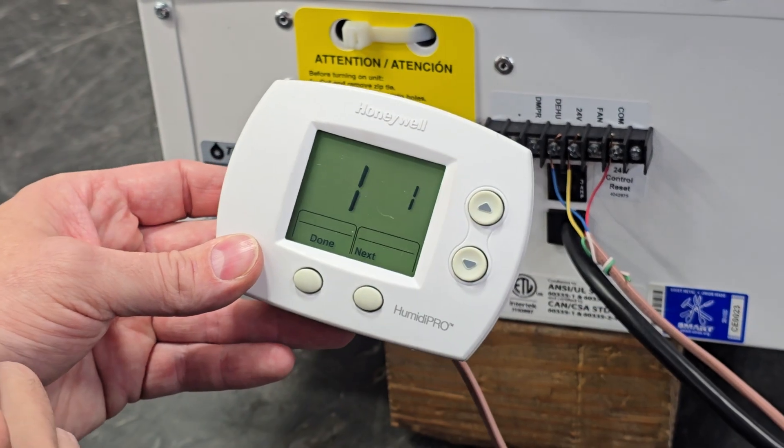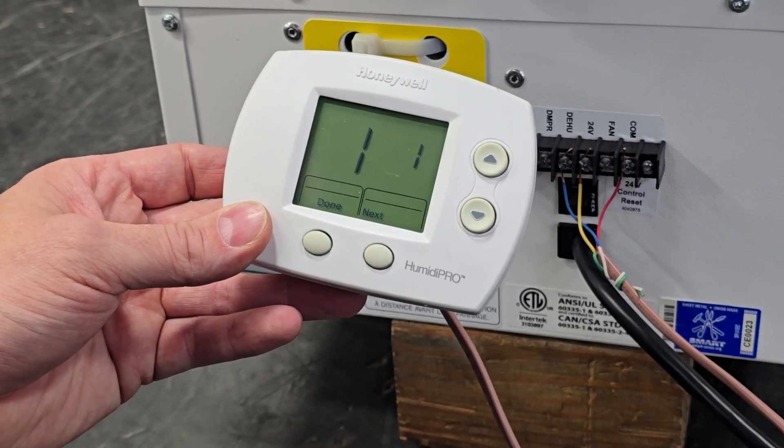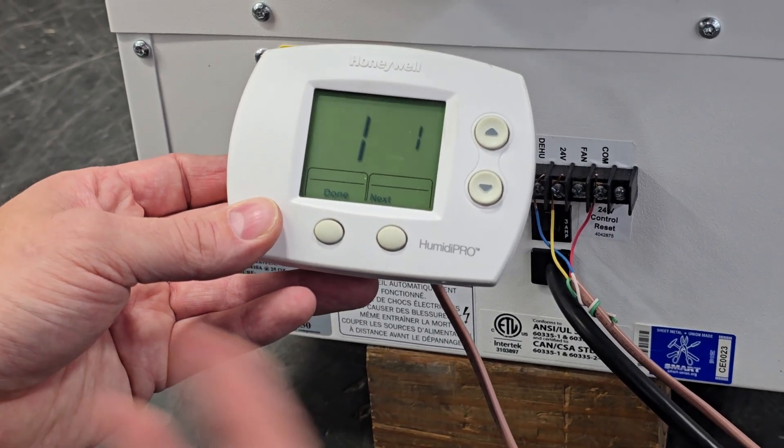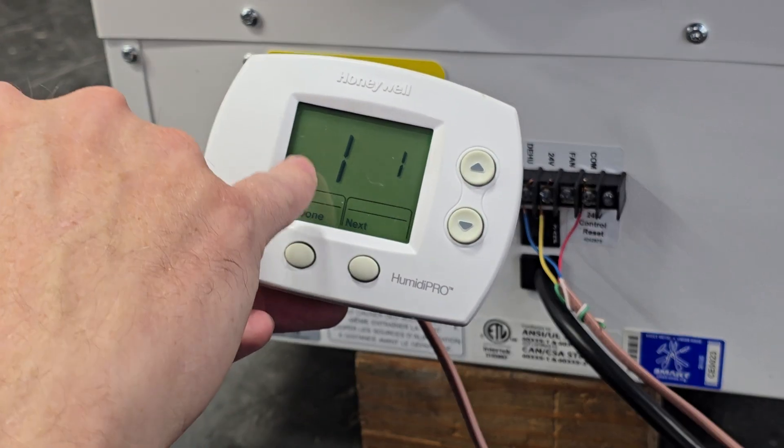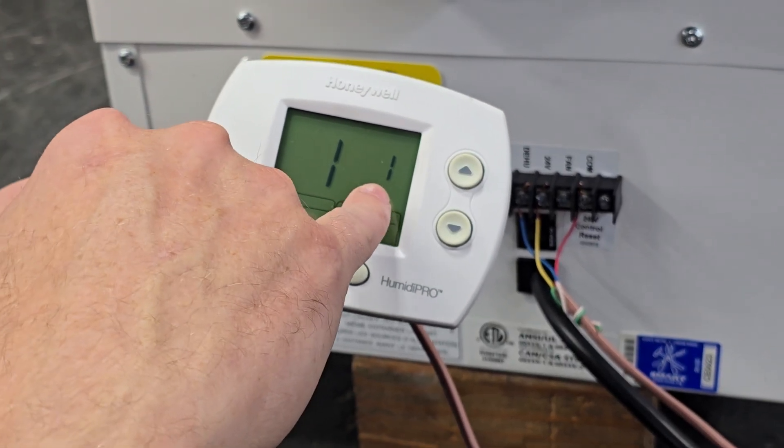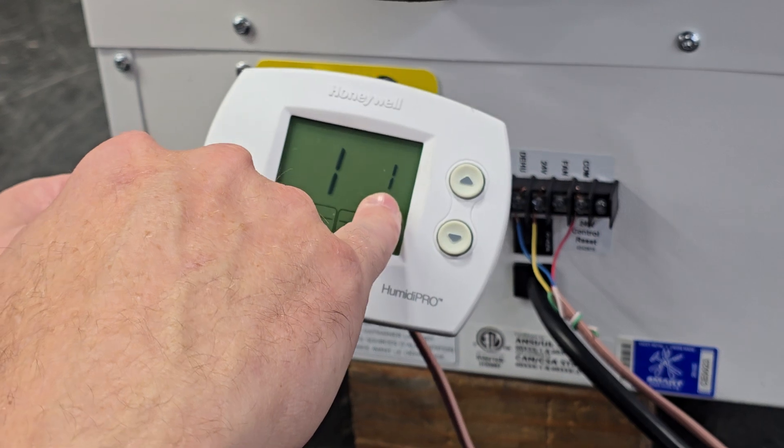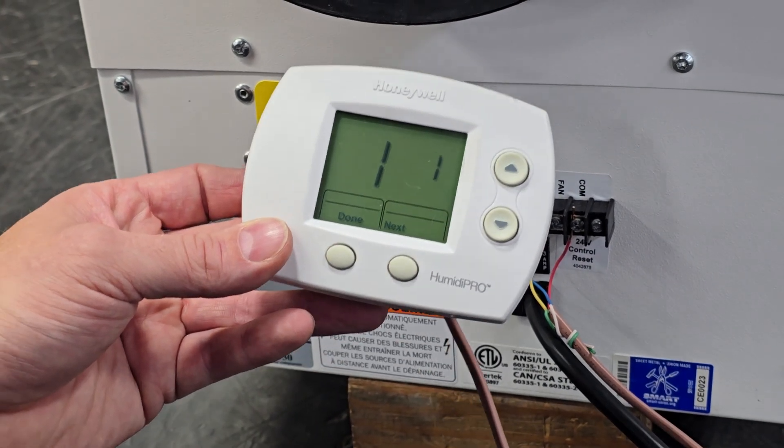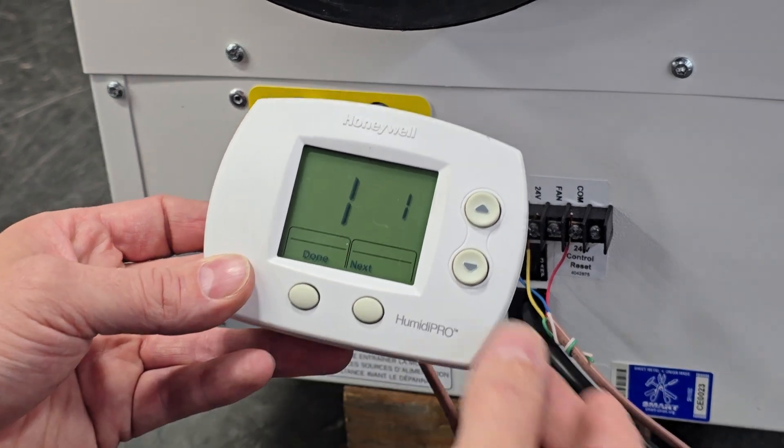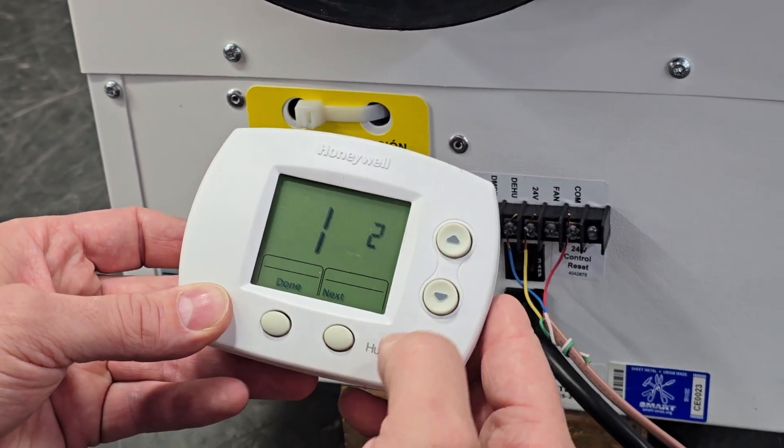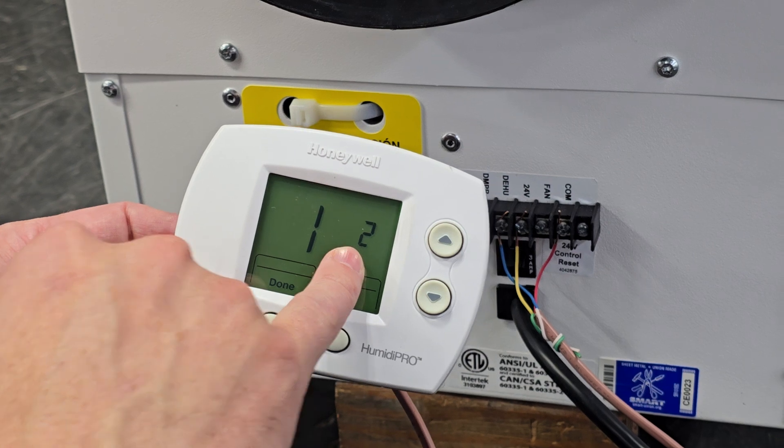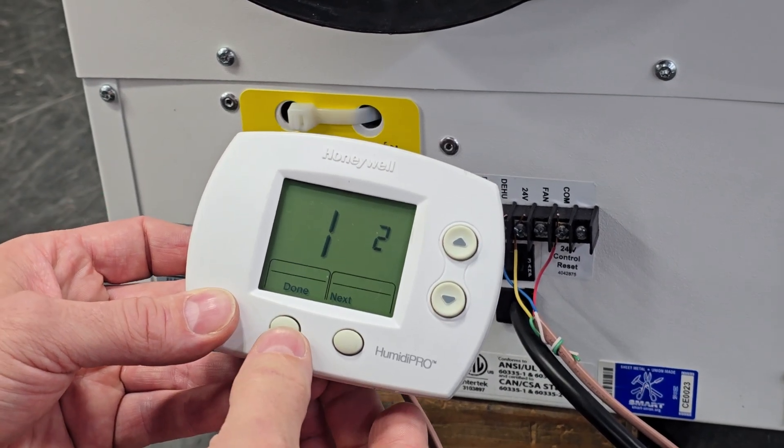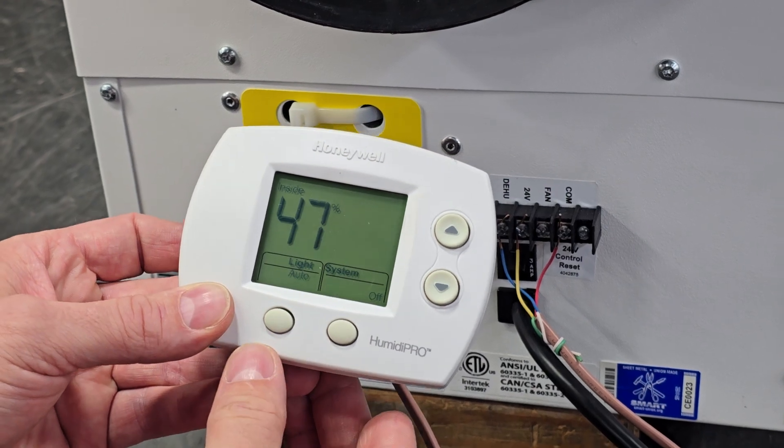These are codes for the different type of control function you want. This is the first function, this is the code on that function. It's set to 1. 1 is actually for a humidistat, so if you're using a humidifier. We're using a dehumidifier, so we want to change that to the number 2. That changes it to a dehumidistat that will operate the dehumidifier. So once we got that done we'll hit done.